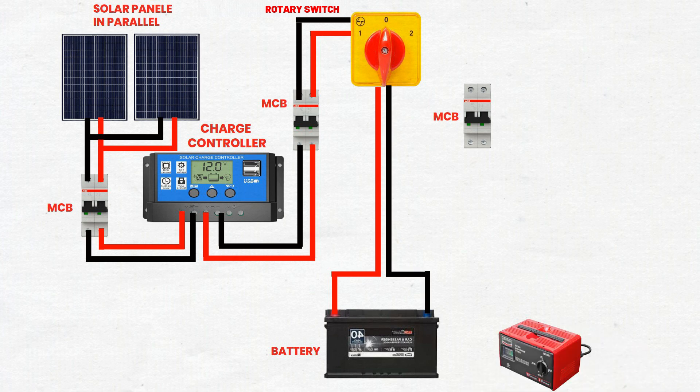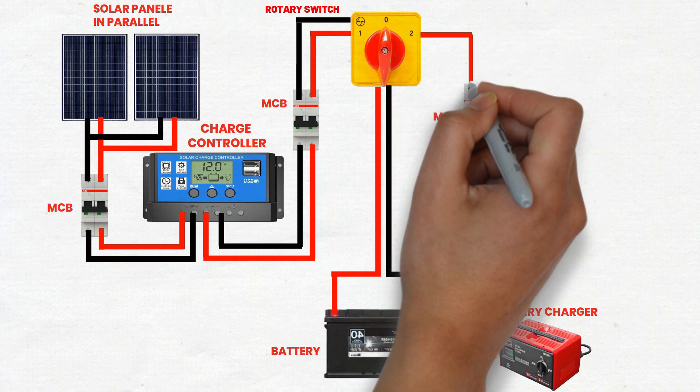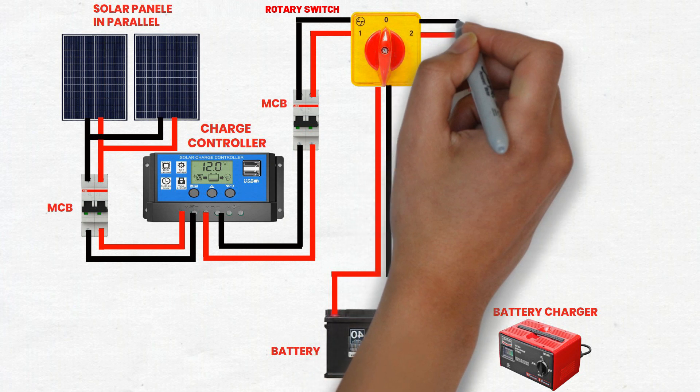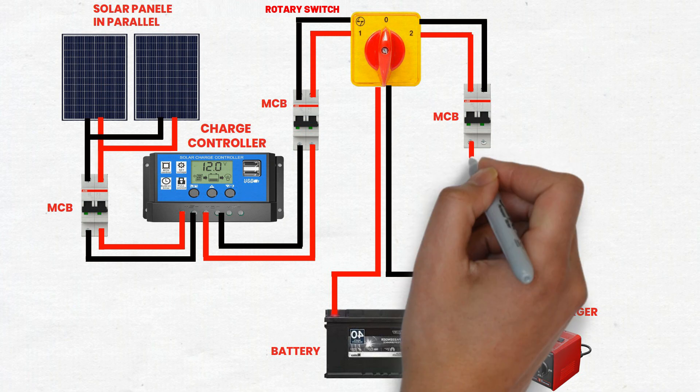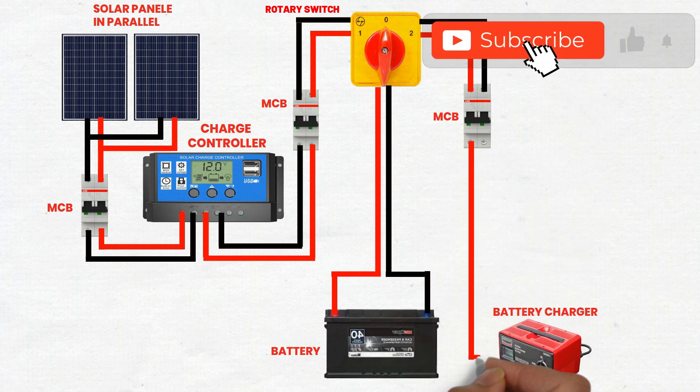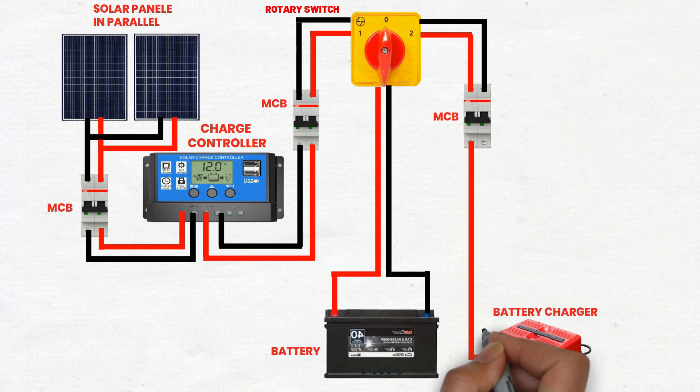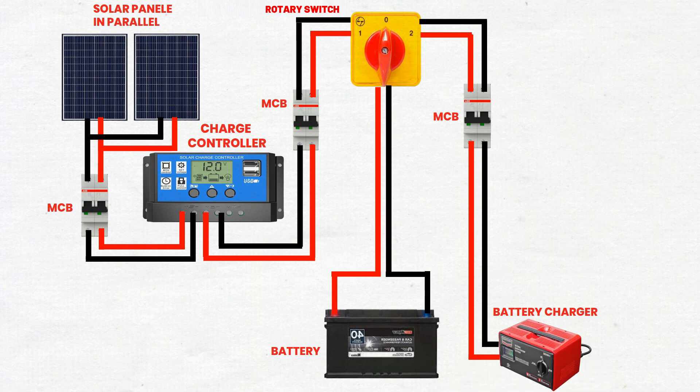Step 6: Connect rotary switch to third MCB. Run cables from the rotary switch to the input terminals of the third MCB. The battery charger maintains the battery charge level, especially if additional charging from an AC source is needed. Connect MCB to charger. Use cables to connect the output terminals of the third MCB to the input terminals of the battery charger. This allows an external AC source to charge the batteries if solar power is insufficient.